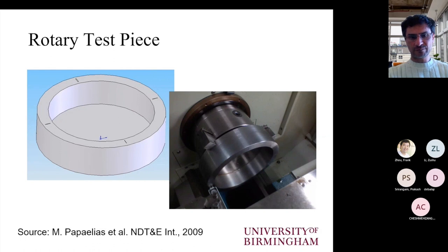So this is the rotary test piece, 4 slots, 2 pairs, 1 pair 2 millimeters deep, the other pair 4 millimeters, that's the turning lathe. And on the bottom left-hand side, you can see the pencil probe that was used for the inspection. Here we did not look at the BZ part of the signal, we only used the probe to assess the depth. So we were looking at just the BX.